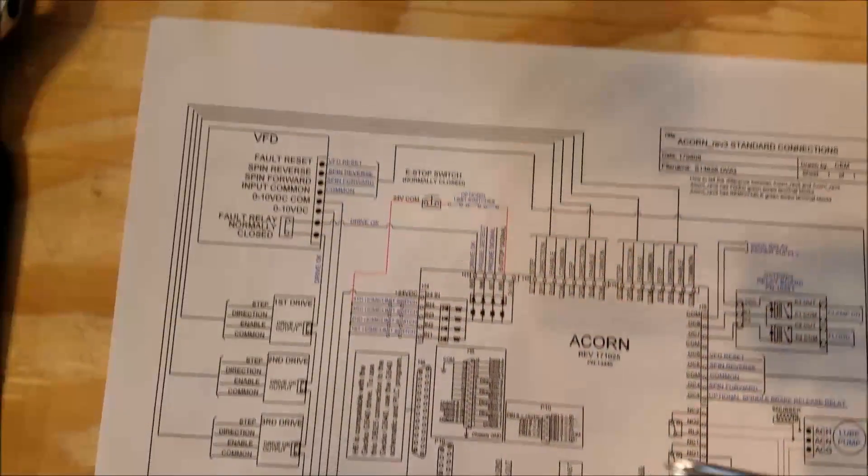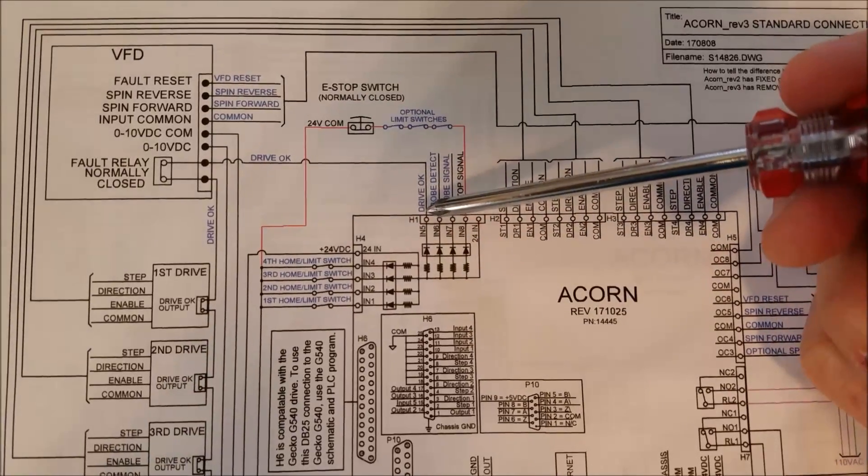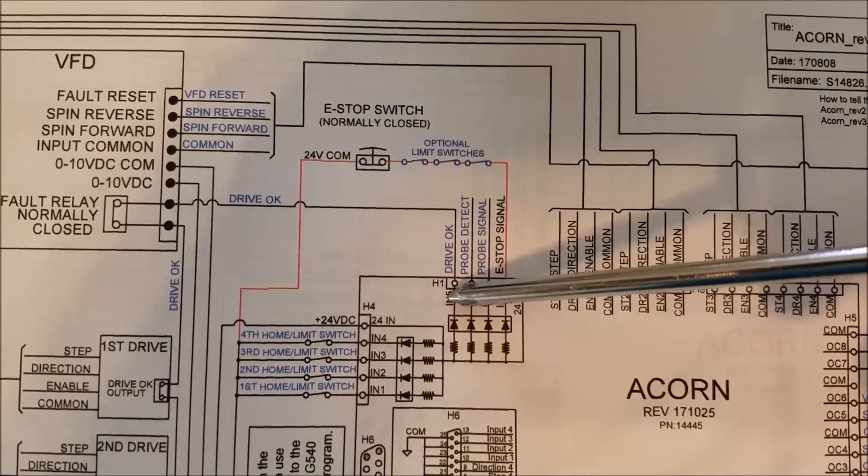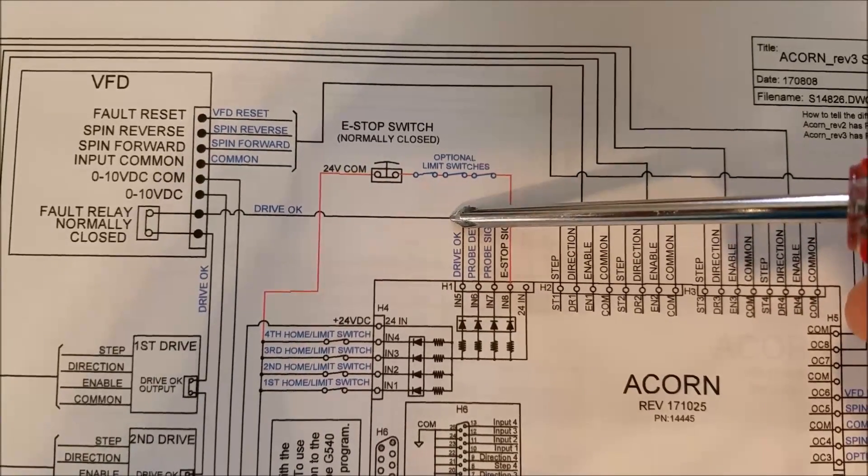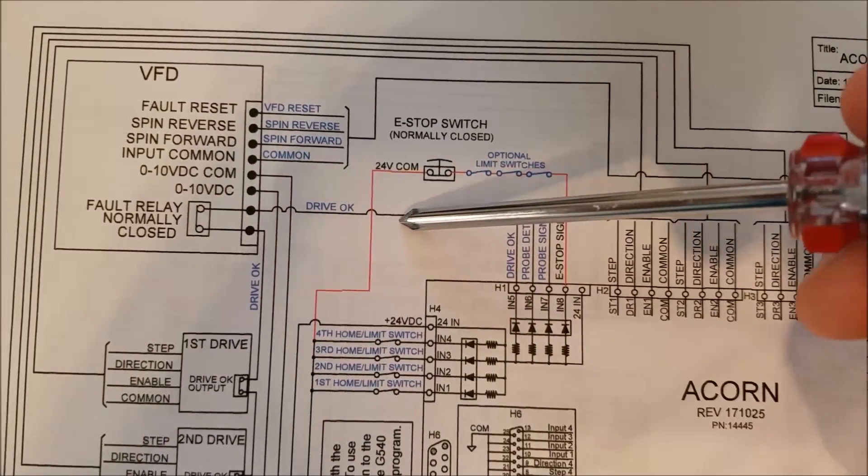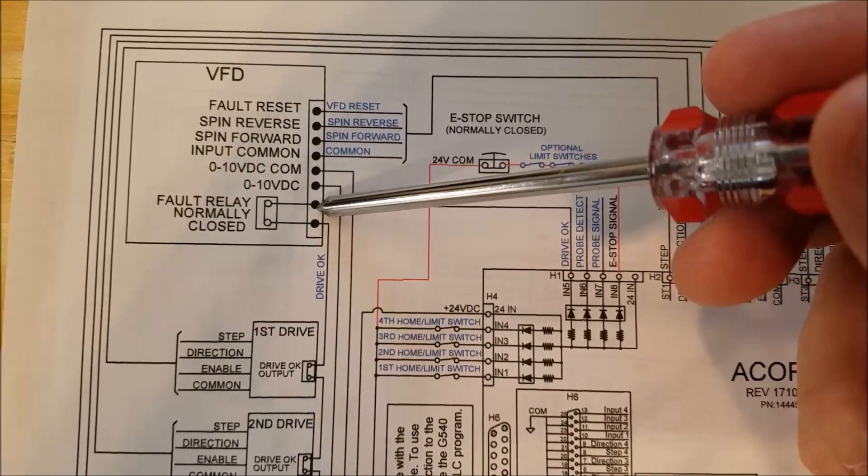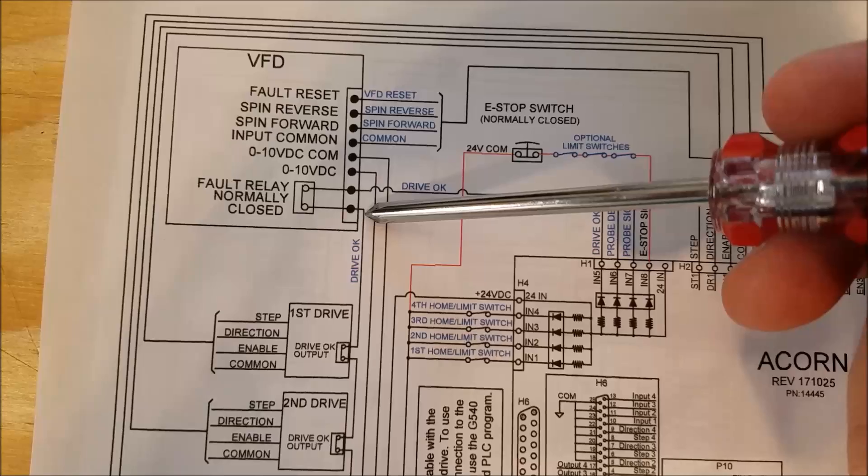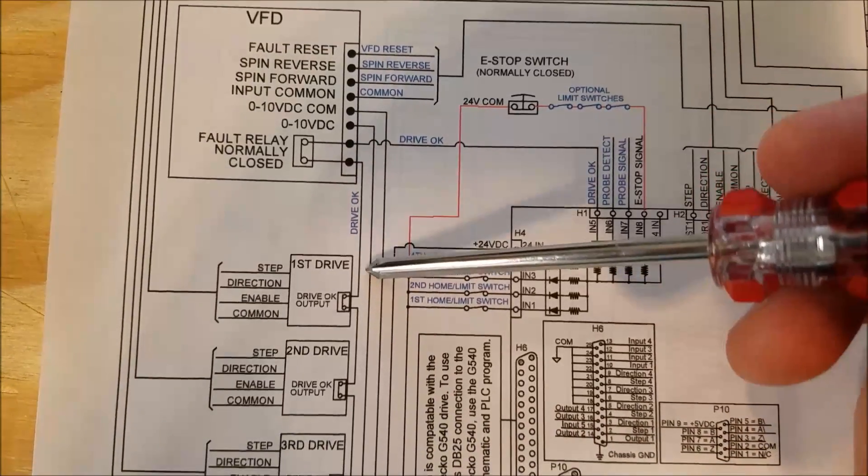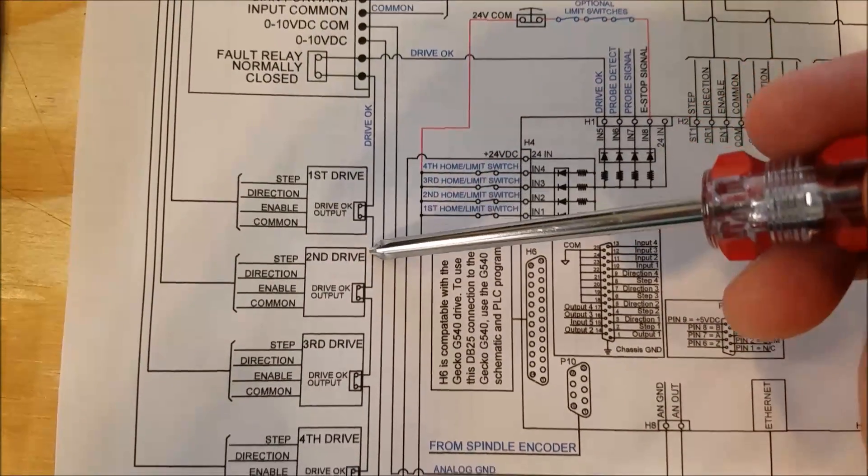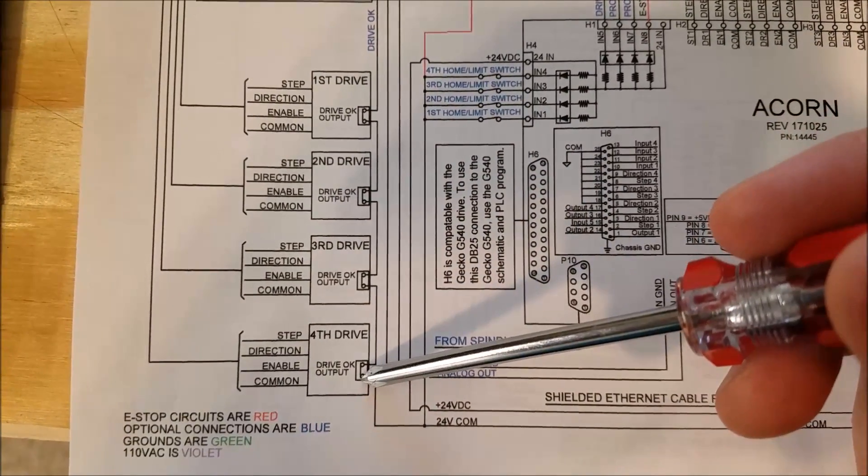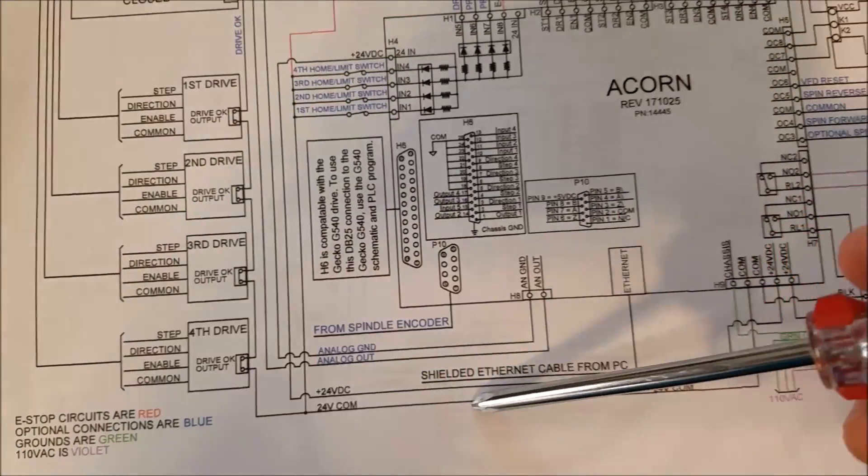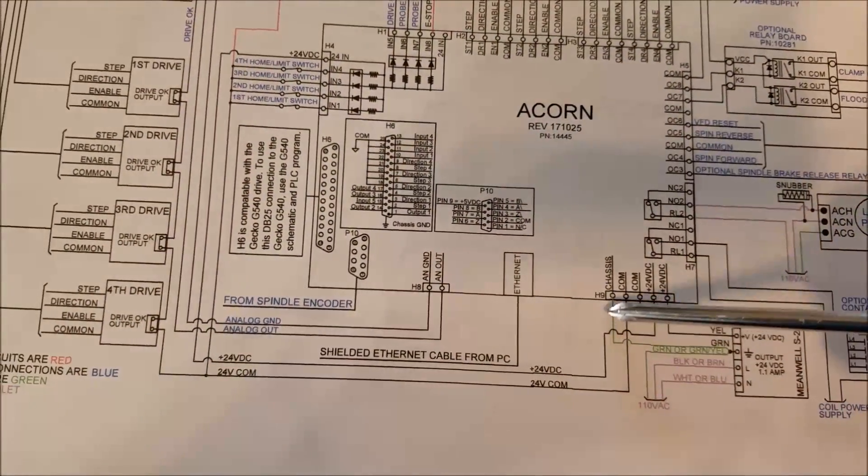So that's what we're going to wire up. What you'll see here is on input five, we have Drive OK. What you do is run the circuit where you come through—in the diagram they show a VFD drive OK, then your first stepper drive Drive OK, your second drive Drive OK, your third drive Drive OK, fourth drive OK. And then finally you return back into common.